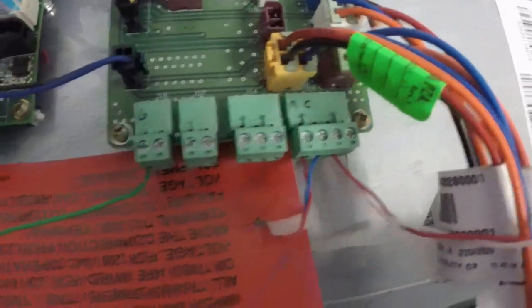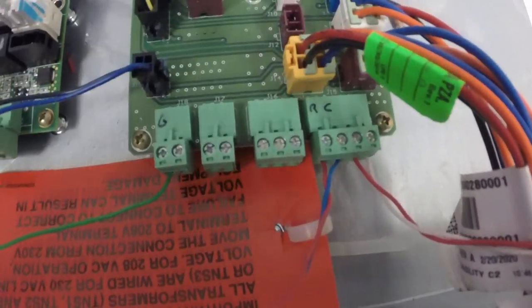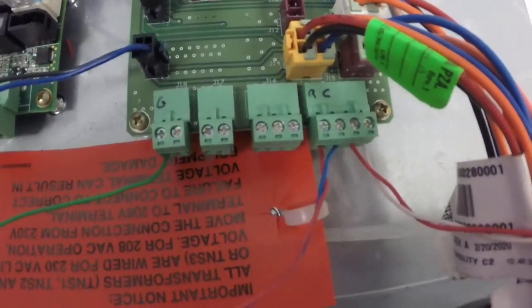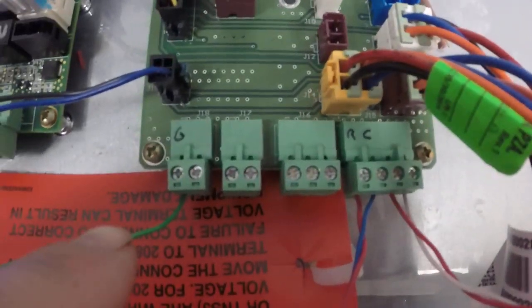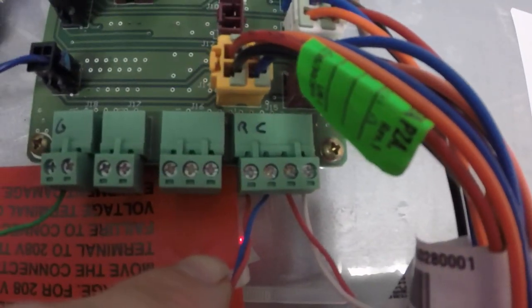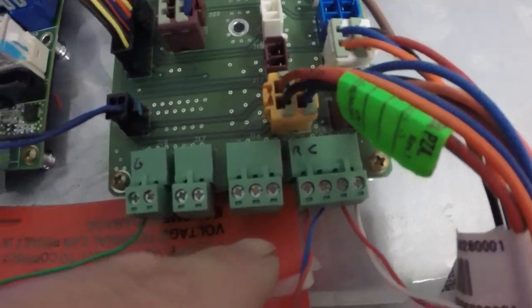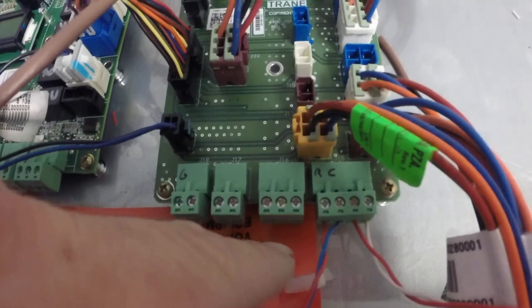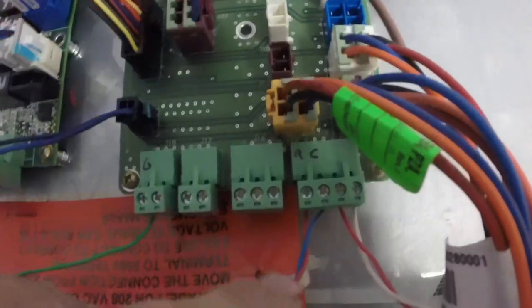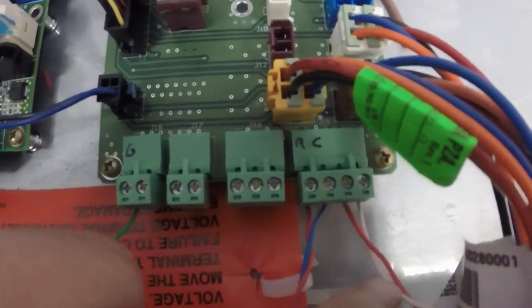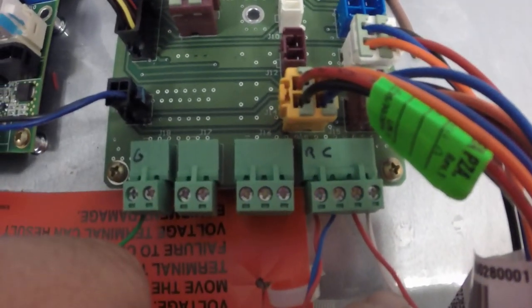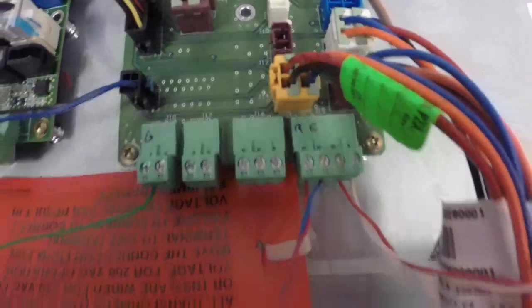From there, you've got some control wire over here on the adapter board, condenser adapter board. I've got my G-terminal labeled. I've got 24 volts and common on pins one and two. This is the J15 plug and then over on the right, pins three and four, we've got our twisted shielded pair.